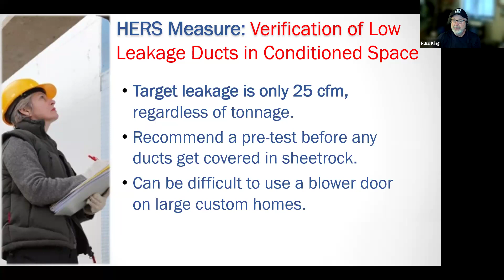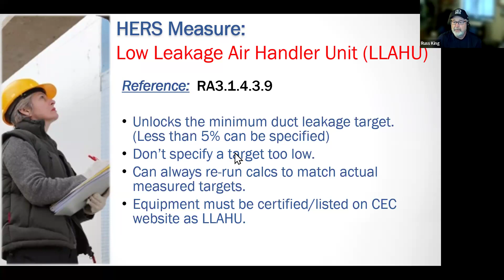Low leakage air handler units. It's been a while since I checked, but last time I looked, it's been a year or two, there weren't any low leakage air handlers on the list. And if anyone has checked lately and knows whether they're there or not, please drop that in the chat. Anyways, it's a certification for the actual air handler. They test the air handler to make sure it's tight. And if they're going to install one of those, it allows them to do other things. It allows you to actually take credit for leakage less than 5%. All right. But they have to install that air handler and you have to test for that leakage, whatever it is, below 5%.